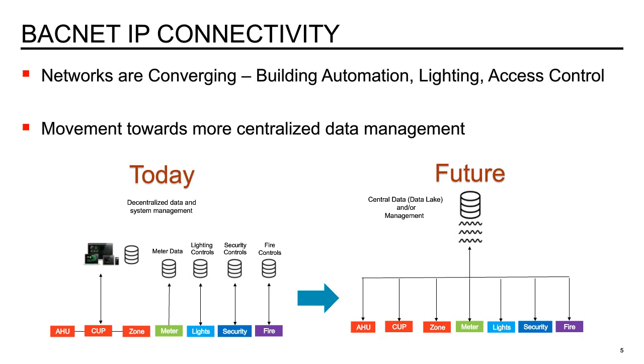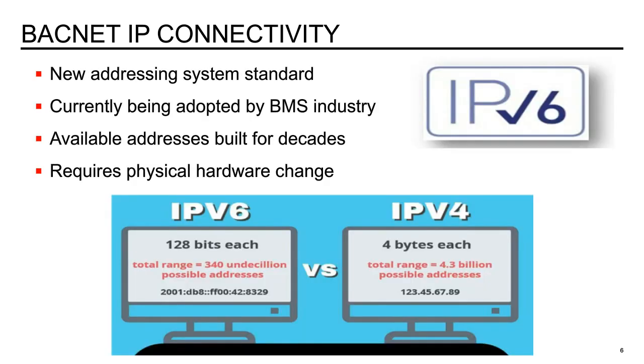As the movement to IP connectivity has grown, the traditional IPv4 protocol that has been used presents some limitations. So BACnet IP has been moving from IPv4 to IPv6 protocol. IPv4 has been around since the early 1980s, and IPv4 addresses comprise 4 numbers, each ranging from 0 to 255. So these would be the traditional IP addresses that you're used to seeing, like 192.168.10.1. The issue is IPv4 has a theoretical limit of 4.3 billion addresses.